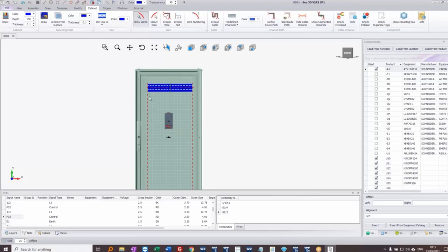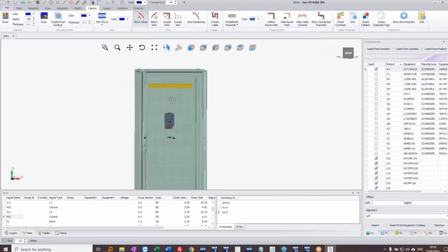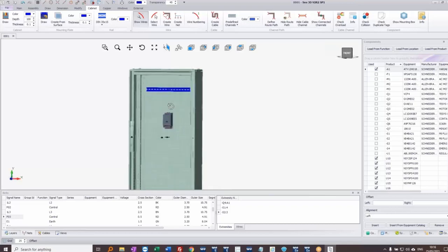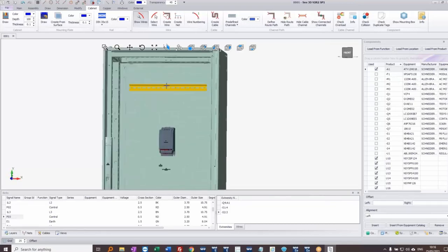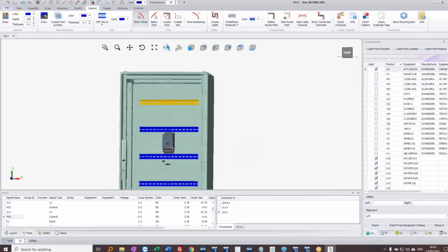When I right-click I get another piece at exactly the same length. I can see object snaps showing the endpoint and midpoint of the backplate and adjacent components, making it easy to line things up. I can double-click a device to move and centralize it on the panel. I can also right-click and use N-Copy in the Y direction — specifying minus 150mm and three copies — to quickly place multiple DIN rails.